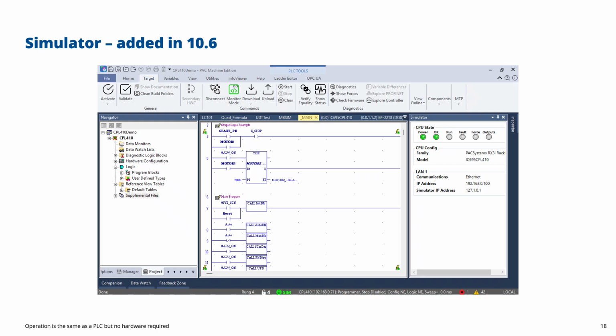The other thing that is a bit difficult to do is simulate the speed of the controller. You may find that what runs on your computer performs at a different level than what's running inside the actual PLC, because we can't easily control how fast the computer runs. So you might find things run slightly slower in a PLC, or if you've got a slow laptop—or faster inside your simulator if you have a powerful one. So there might be some timing differences there.